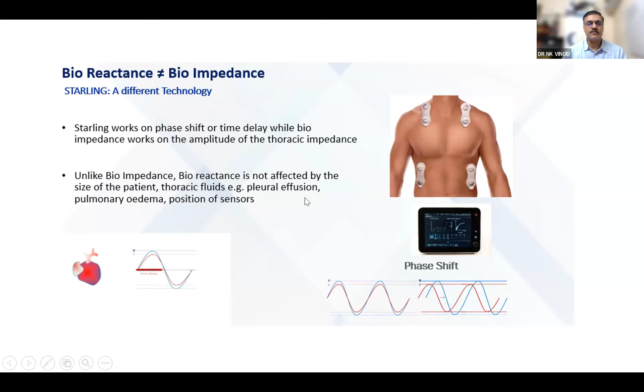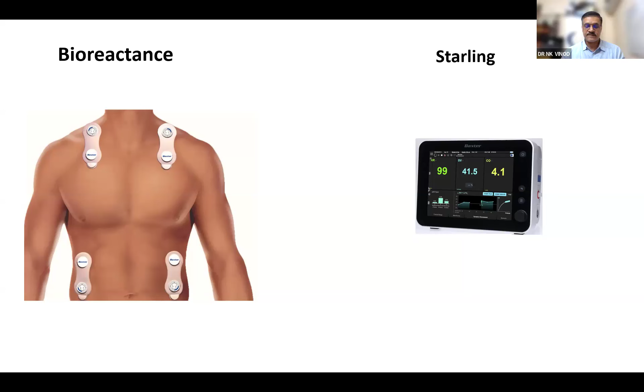The first version of the non-invasive cardiac output monitor, or the NICOM, was manufactured by Cheetah Medicals in the Newton Center, Massachusetts. This was used as a reference standard, which has been validated with other cardiac output monitoring systems like the pulse contour analysis and the pulmonary arterial catheter. The initial versions of this monitor provided cardiac output readings, which were averaged over 30 seconds. Hence, there were some concerns regarding its ability to track rapid changes in the stroke volume. The present Starling device has an averaging of about 8 seconds.